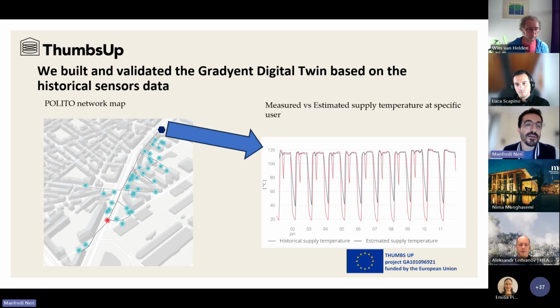On this slide you can see a proof of the accuracy of this tool: a comparison between the historical supply temperature measured at one of the building locations, and the supply temperature estimated by the digital twin itself. You can clearly see the two temperatures are very close when the network is operating, when there is actually flow in the pipes. The only time steps where you see larger differences are when the network is not operating, when it's off and there's no water flowing in the pipes. This proves the accuracy and quality of the thermal hydraulic model.